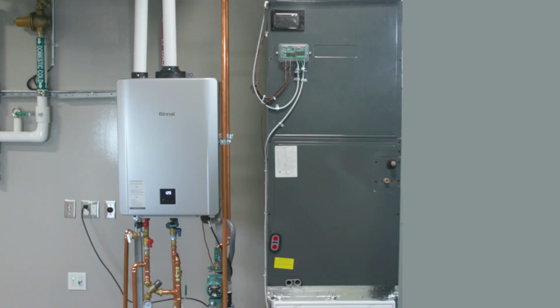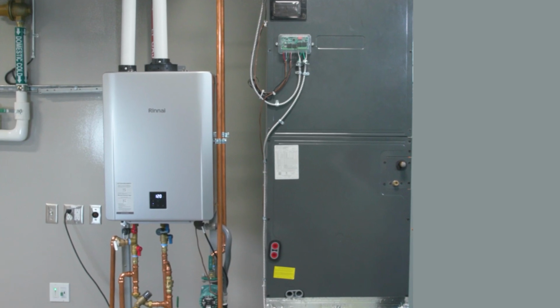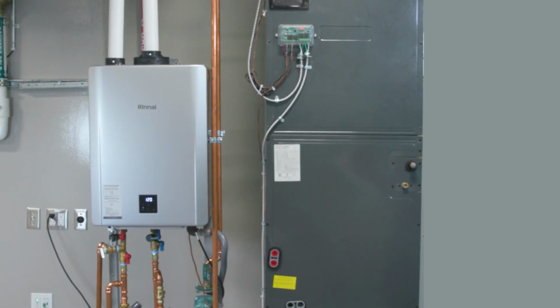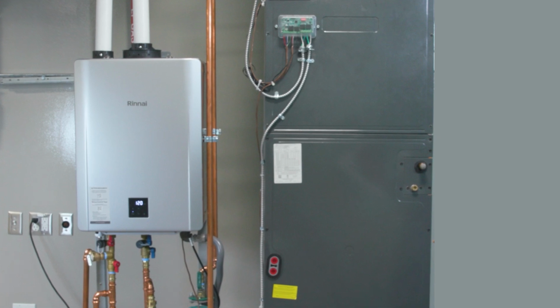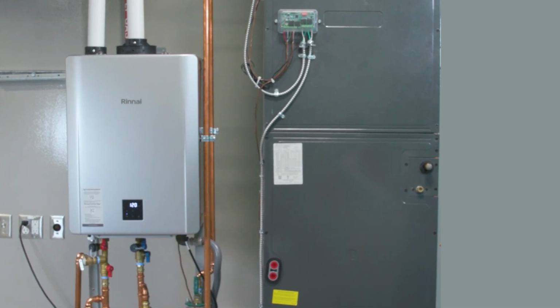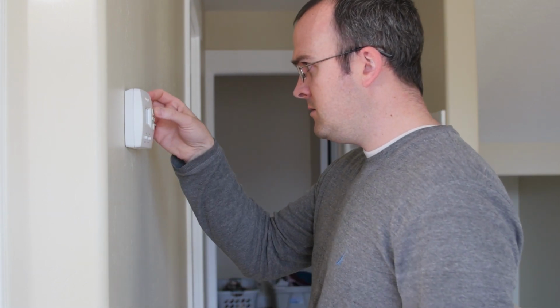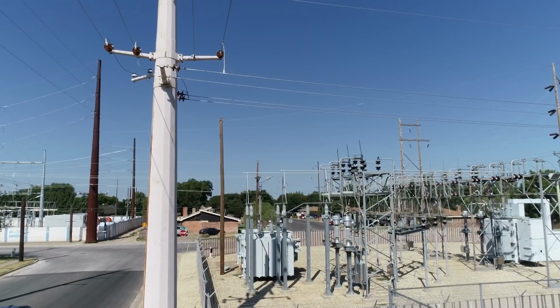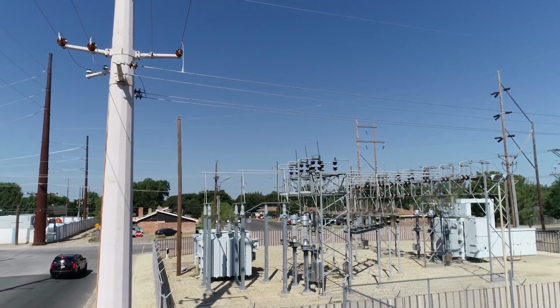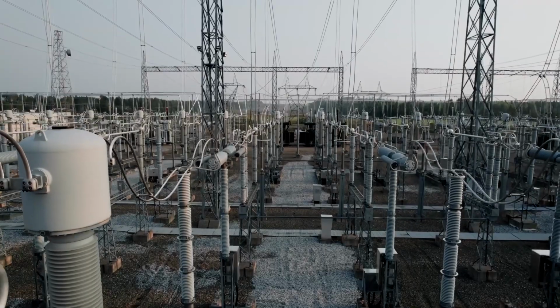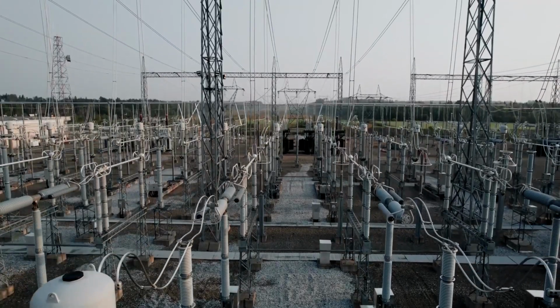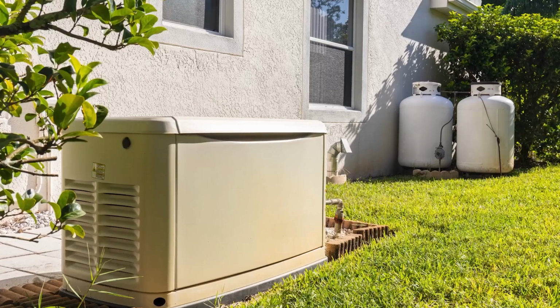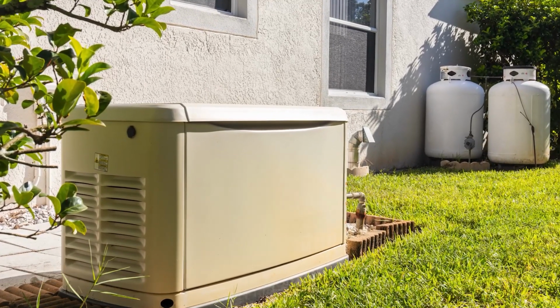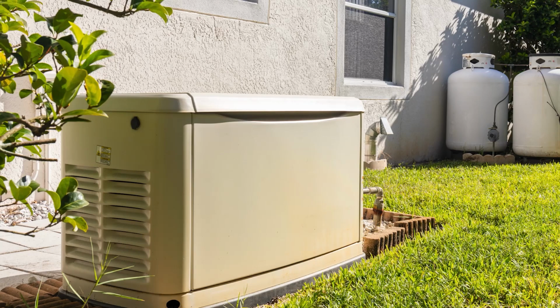The Heat Pump Companion reduces heating costs. By switching from the inefficient and expensive electric heat to propane or natural gas-powered hydronic heat, your customers save money by reducing their electricity usage. It also reduces electric demand. With less demand and reliance on the electric grid means dependable heat during load shedding periods. In residential applications with a standby generator, your customer may be able to downsize to a smaller generator solution and still meet the needs of the household.